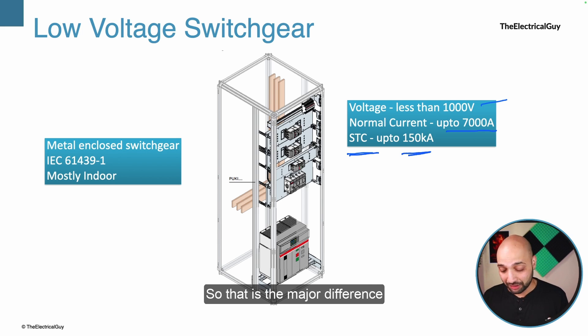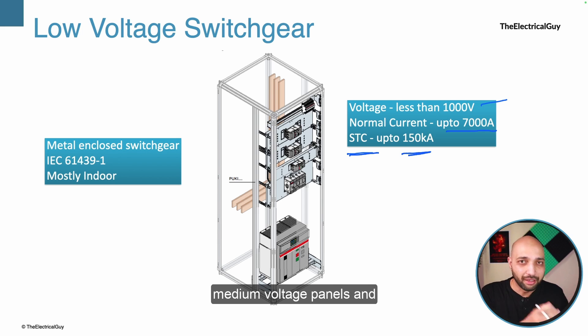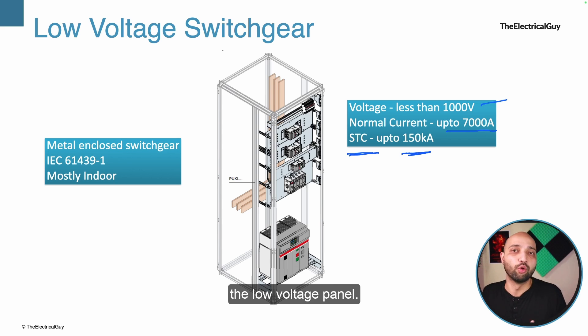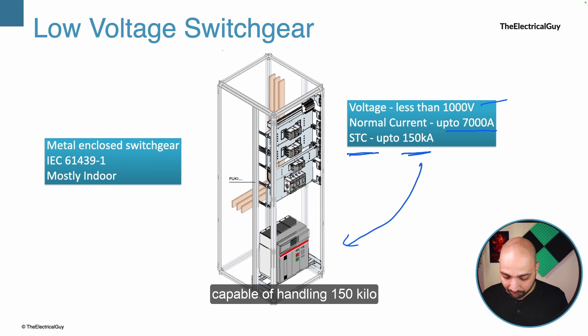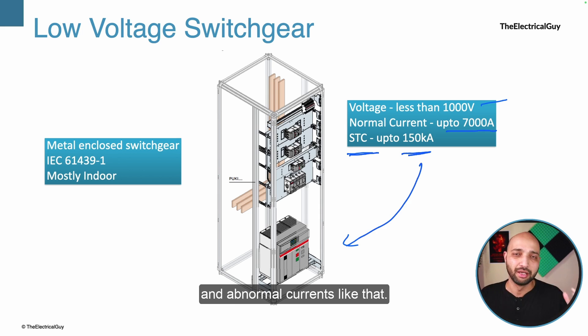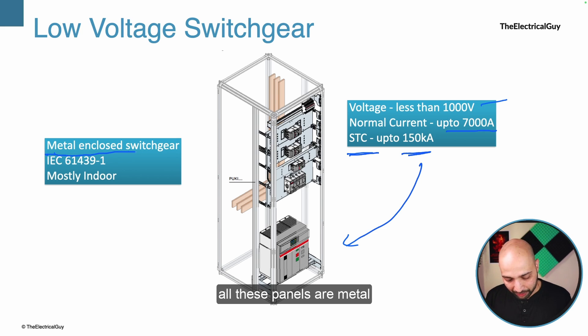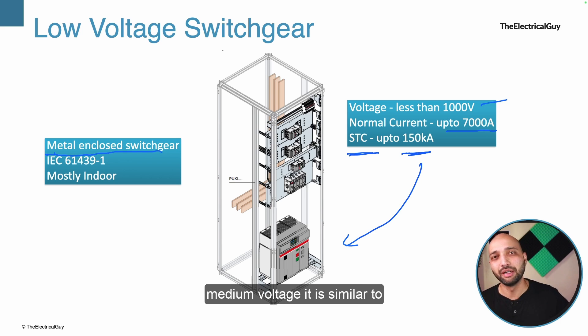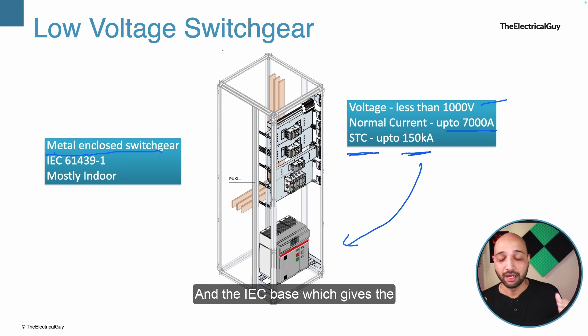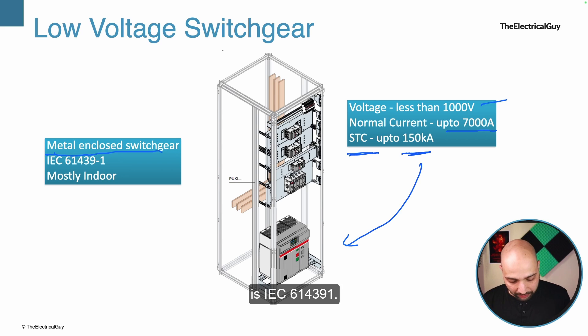That is a major difference between medium voltage and low voltage panels. There are breakers capable of handling 150 kA, 120 kA, and 83 kA abnormal currents. All these panels are metal enclosed switchgear, similar to what we have seen in medium voltage. The IEC standard that gives general guidelines for low voltage switchgear is IEC 61439-1, and these panels are mostly indoor panels.